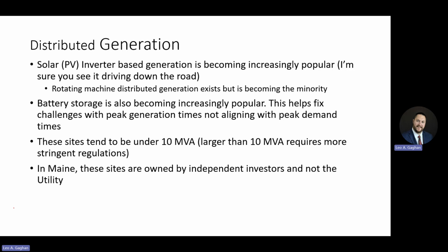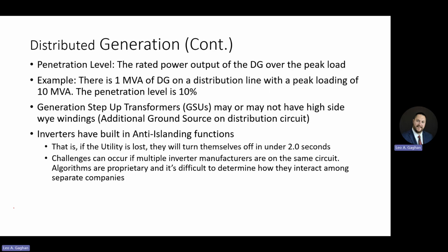And then in Maine, these sites are generally owned by independent investors and not the utility themselves. That's not the case everywhere. It is kind of most places, but there's a thing called deregulation in the state of Maine that kind of separates the utilities and the generation. So like a Central Maine Power or a Versant typically wouldn't own those solar facilities. Those are usually owned by independent power producers that sell the power to the utility. So like I said, not the case everywhere, but in the state of Maine, that's usually the case. Some more on distributed generation, a term, penetration level: the rated power output of the distributed generation over the peak load. So for example, if you had 1 MVA of distributed generation on a line with a peak loading of 10 MVA, penetration is 10%.